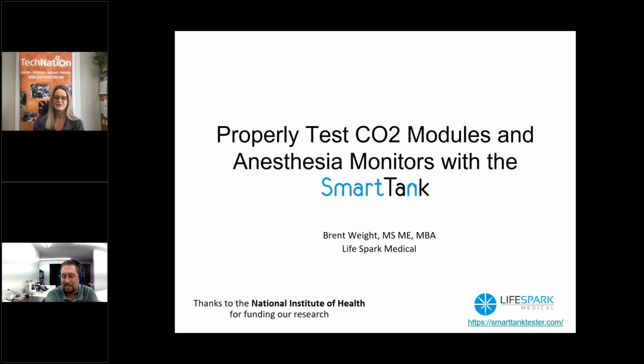During today's demo, we will learn how the SmartTank facilitates proper testing of your CO2 modules and gas monitors while saving time and gas. The SmartTank is an all-in-one testing device for CO2 gas modules and anesthesia monitors. The SmartTank automates the testing of these devices, providing better testing in less time using less gas, all documented in detailed test reports. With an easy-to-use interface, the SmartTank has a preloaded test sequence that will walk the operator through each step quickly and seamlessly. All the hardware needed to test gas modules is built into the SmartTank. That's replacing the need for separate gas regulators, flow meters, syringes, tubes, pressure gauges, barometers, and even the service manual.